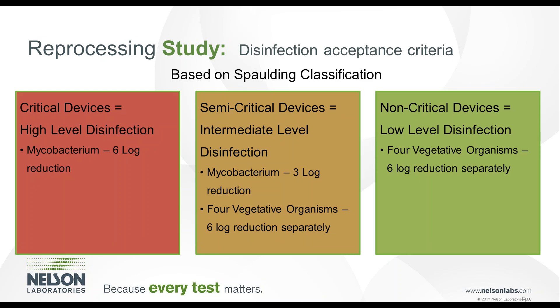For a critical device requiring high level disinfection, the requirements are pretty much the same across the U.S. and Europe: a six log reduction of mycobacterium species. For semi-critical devices requiring intermediate level disinfection, it's the same organism but only a three log reduction, plus four vegetative organisms requiring a six log reduction. For non-critical devices, low level disinfection requires four vegetative organisms with a six log reduction.